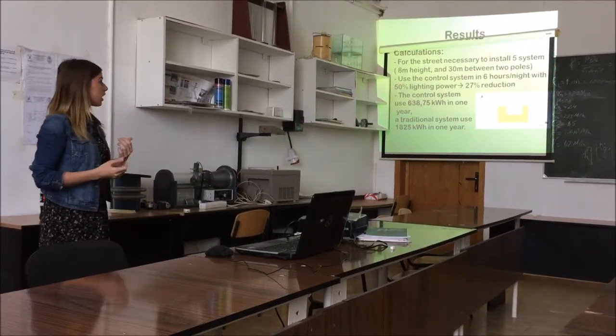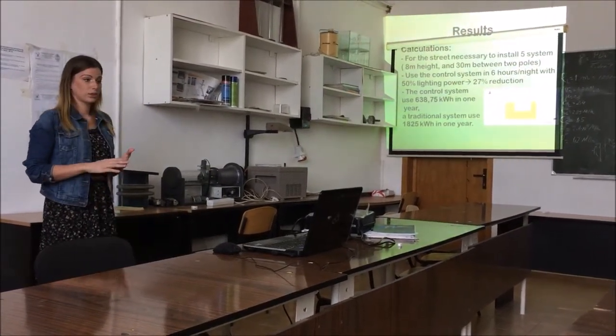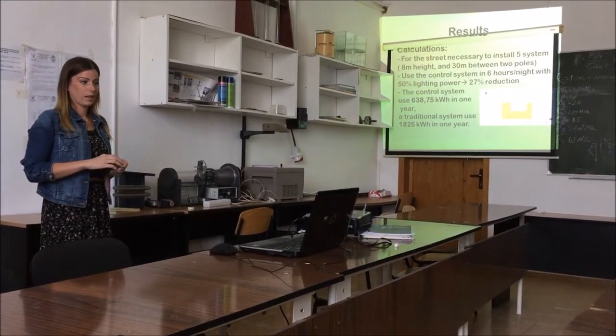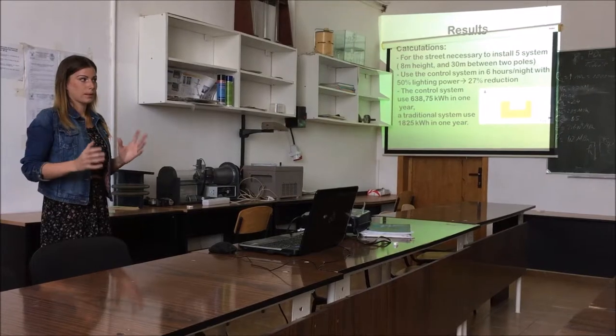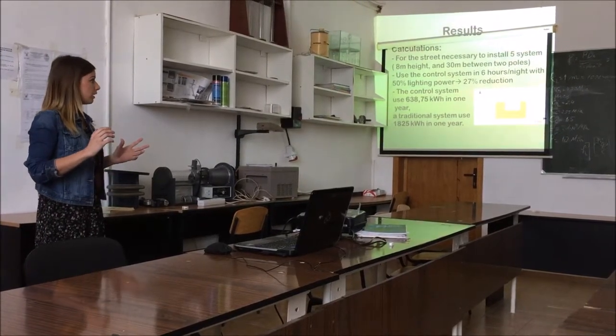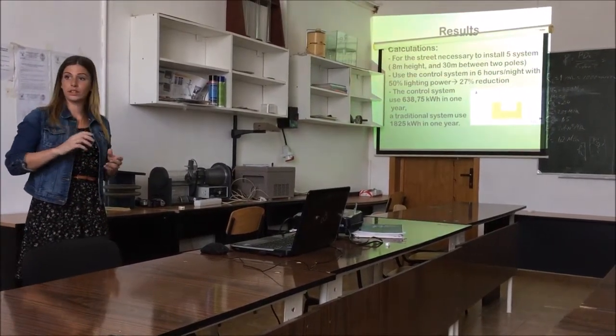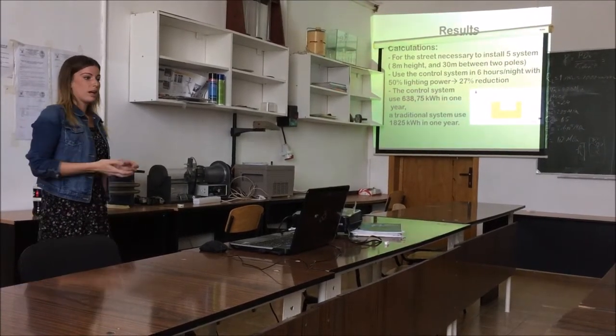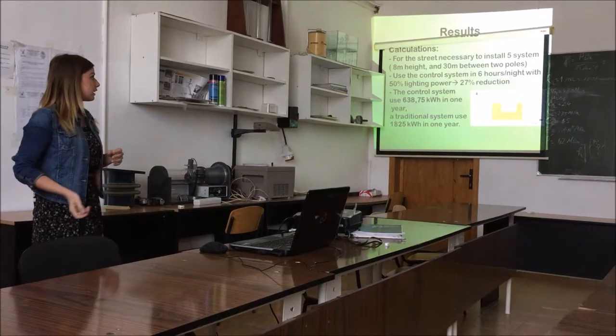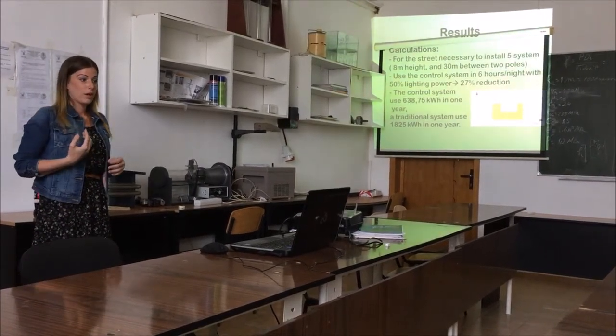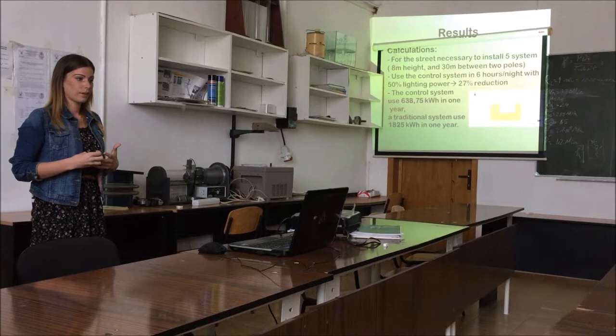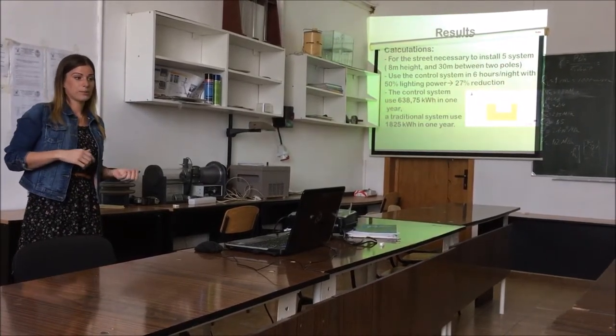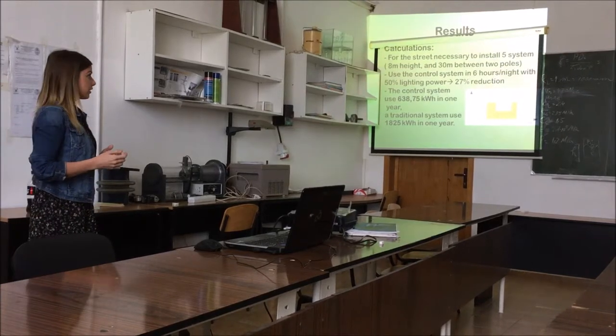The results from the calculation: it's a short street and the best solution is that the distance between two poles is 30 meters and the height of the poles is 8 meters.